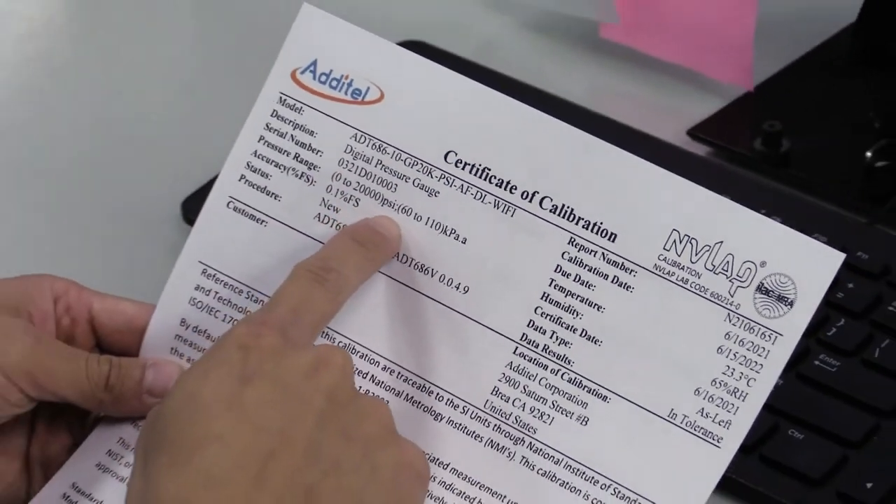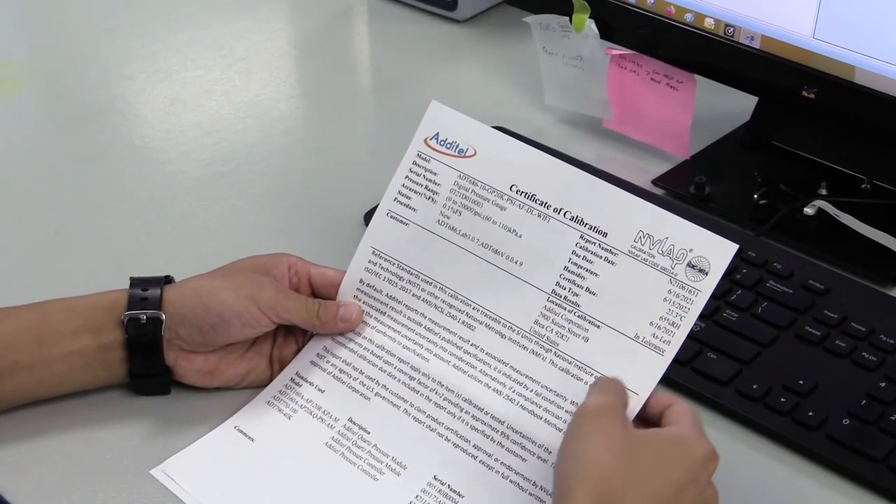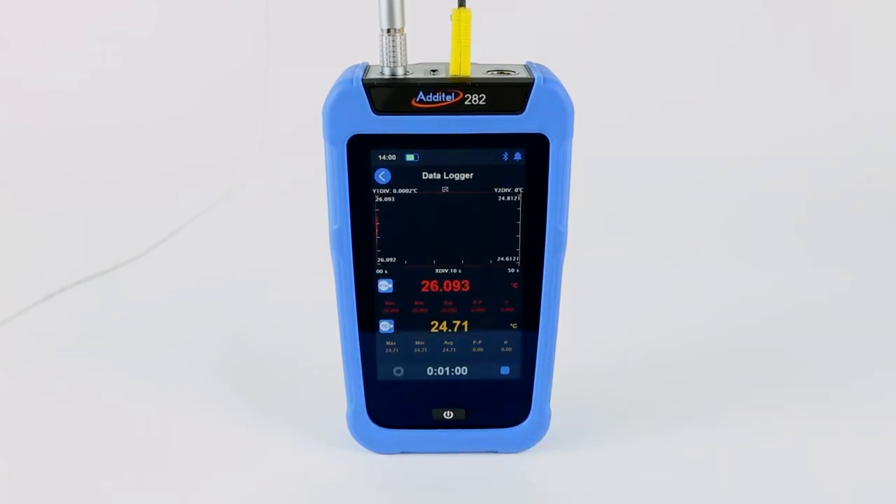Every meter is shipped with an NIST traceable NVLAP accredited certificate of calibration with data. Accurate temperature measurements can be tricky, but you will find that Additel is once again making metrology simple with this easy-to-use ADT282 dual-channel reference thermometer readout.